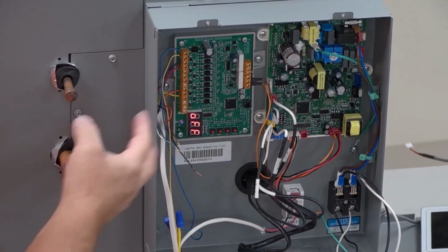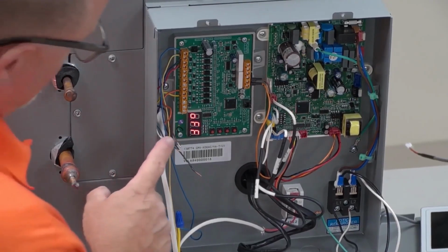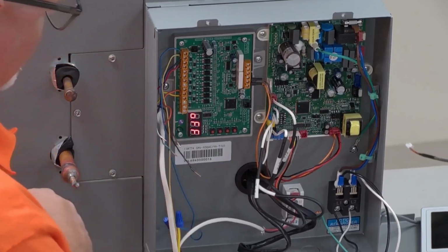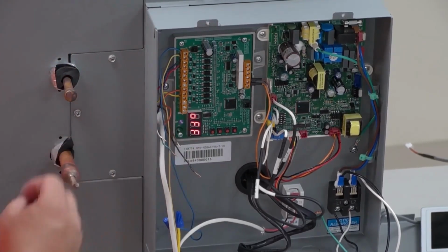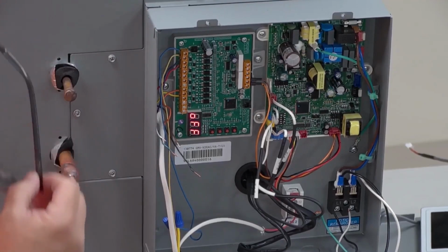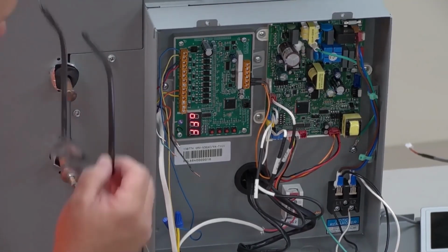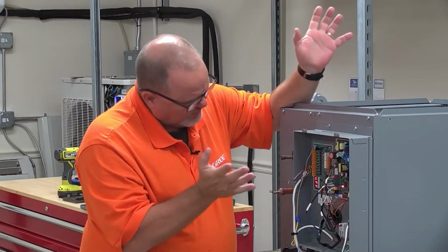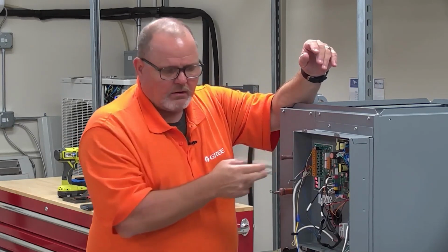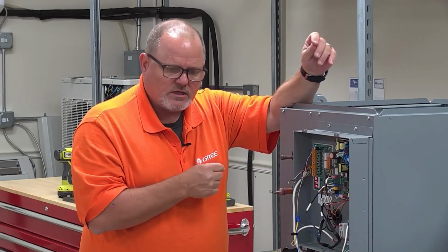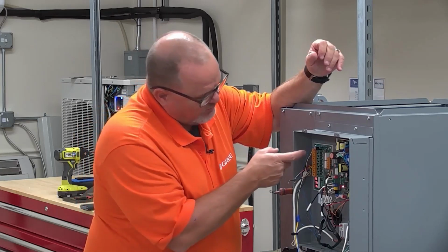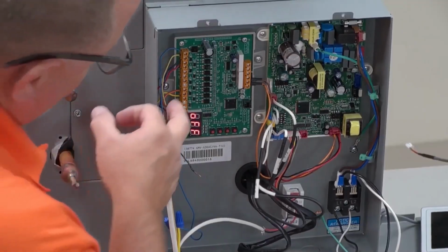But since we're using it in the dual fuel application, we don't need to set that. And that's why you'll see all these different thermostat wires hanging off of here, because I'm going to use this to simulate doing a 24-volt adapter as well. So again, back to repeating one more time, you're going to put your 24-volt power from your furnace. That's going to go to TC and TR. Then you're going to have your R and your C going to your stat. You're going to have your B and your Y, and that's it.